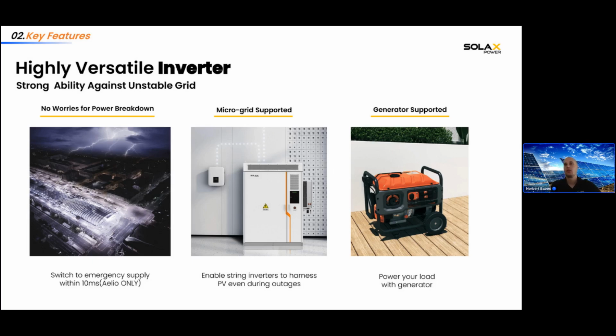It also has the EPS function, the AELIO, which we talked about. So if you have a power outage, it can switch to off-grid mode within 10 milliseconds. And also, if you have an older system or you already have a PV system, you can just connect those old inverters, like string inverters, to the EPS side, and then you can harvest that energy to supply the loads or charge the batteries.